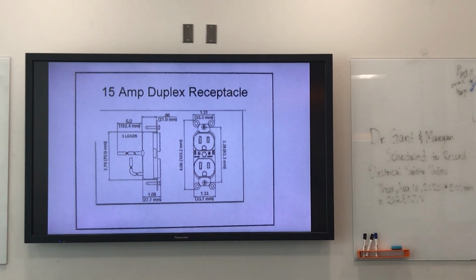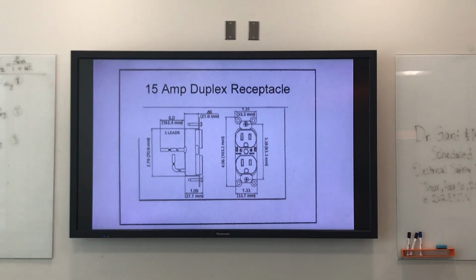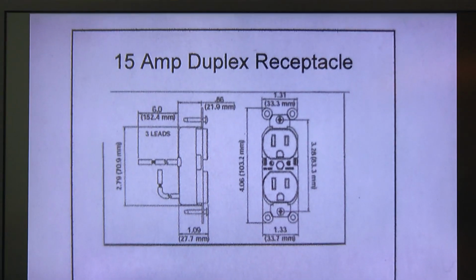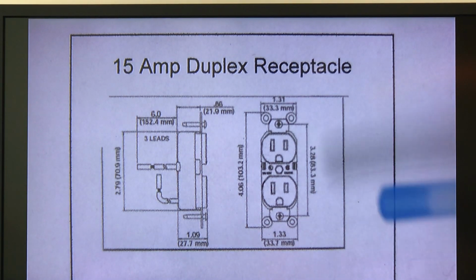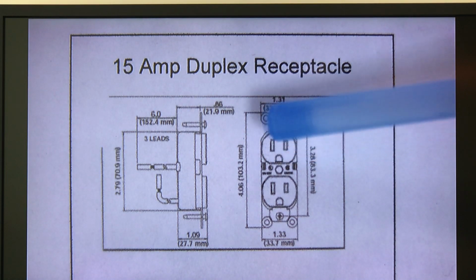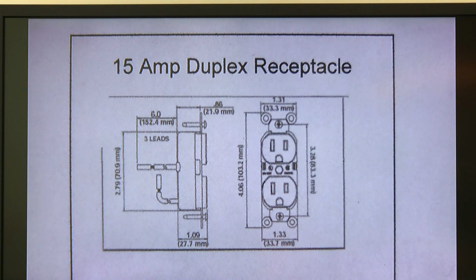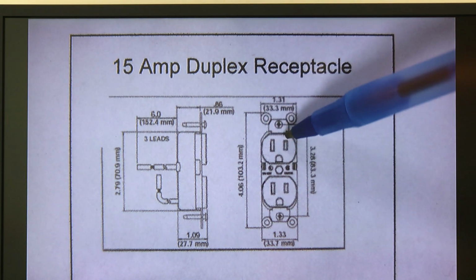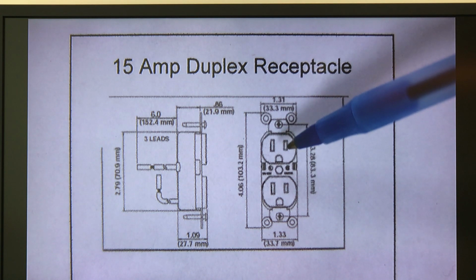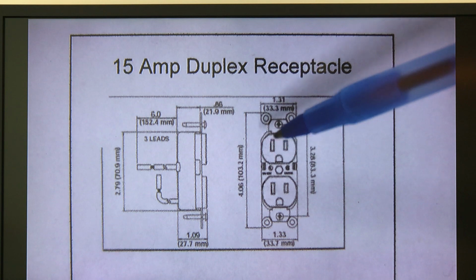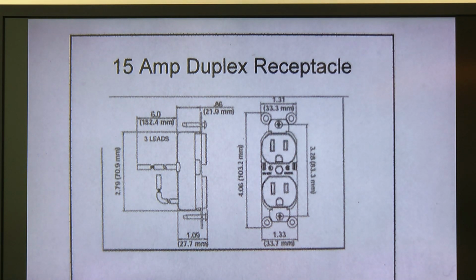Any kind of new material, any kind of new work, an electrician would call it, will have two different types of receptacles. These are called duplex receptacles because, as you can see, there are two of them. The thing I'd like to draw to your particular attention is that of these devices, these two blades here, if you will notice, they are not the same size. This one on the right-hand side, the way you're looking at it, is a little bit shorter than the one over here on the left, and that's no accident.